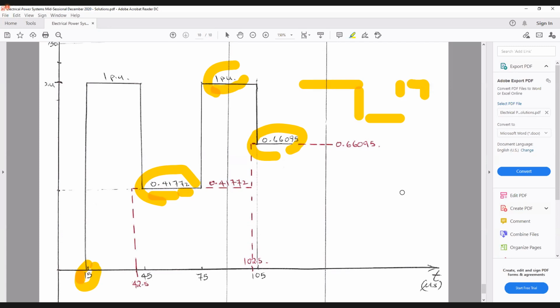So in other words, what you are seeing here is that the line is charging. That's the point. And you would also note for the cable, right, each time a ray comes across, the cable's voltage is also increasing. So the cable is also coming up to 1 per unit, all right? Which comes back to what we presented in terms of the theory, and we use the terminology in the industry where we talk about line charging. So you talk about charging the line, yeah? This is really what is happening, all right?